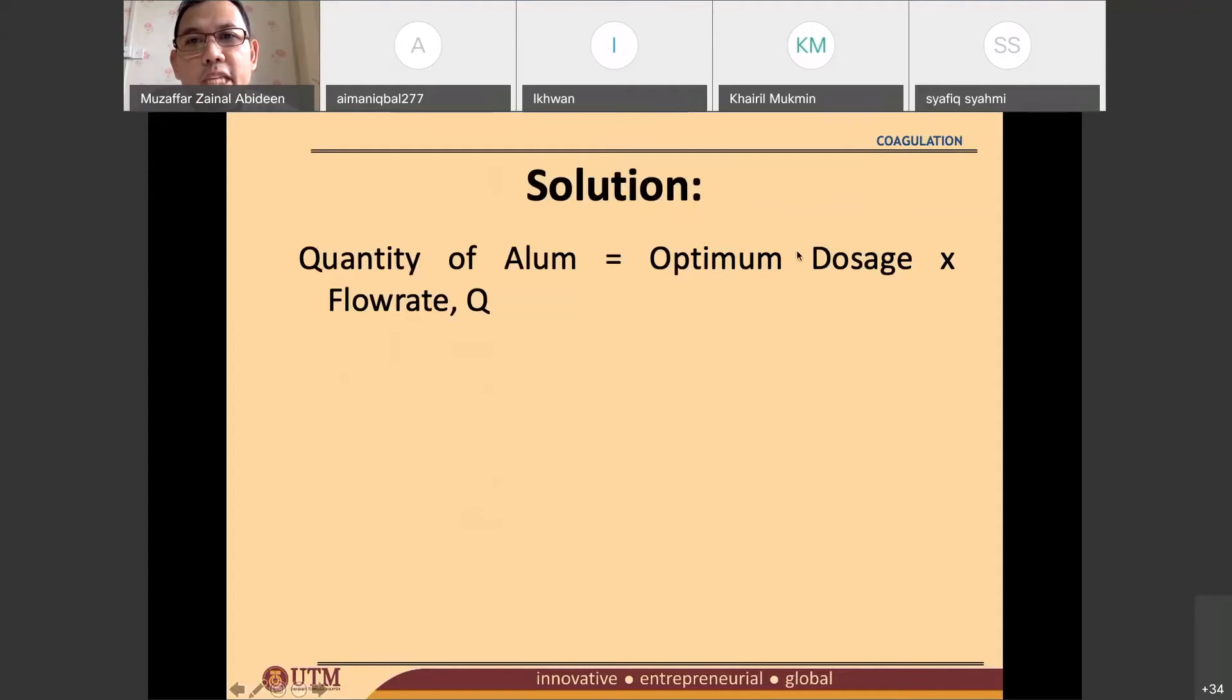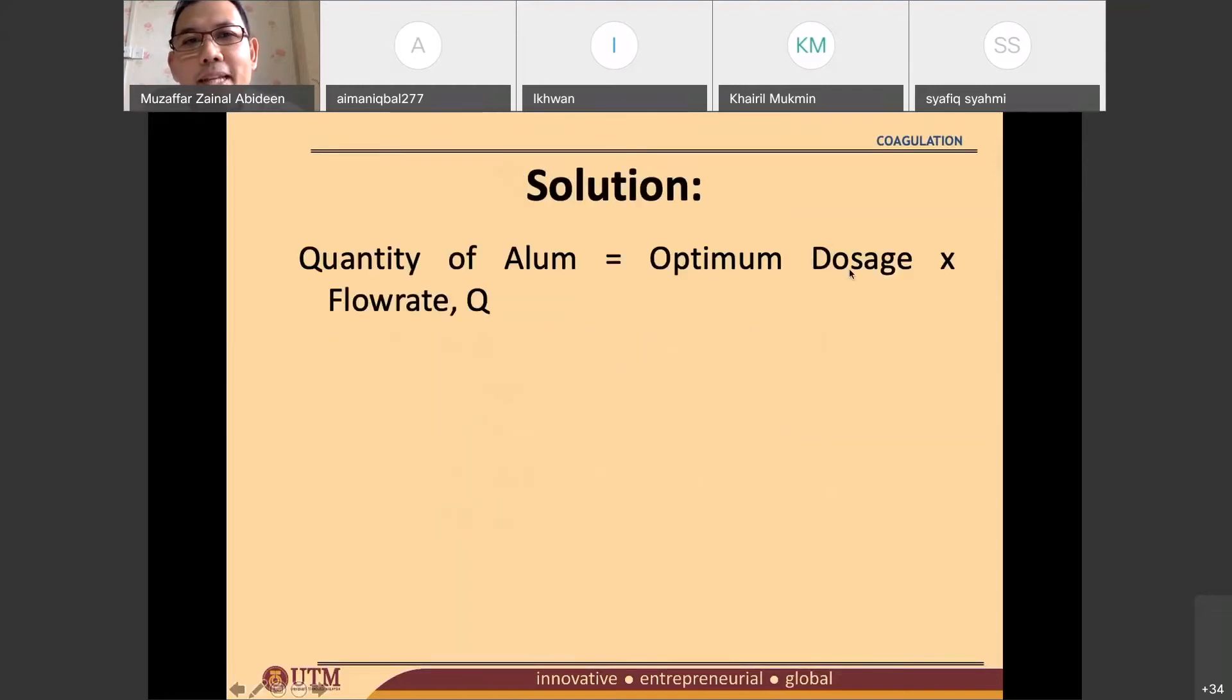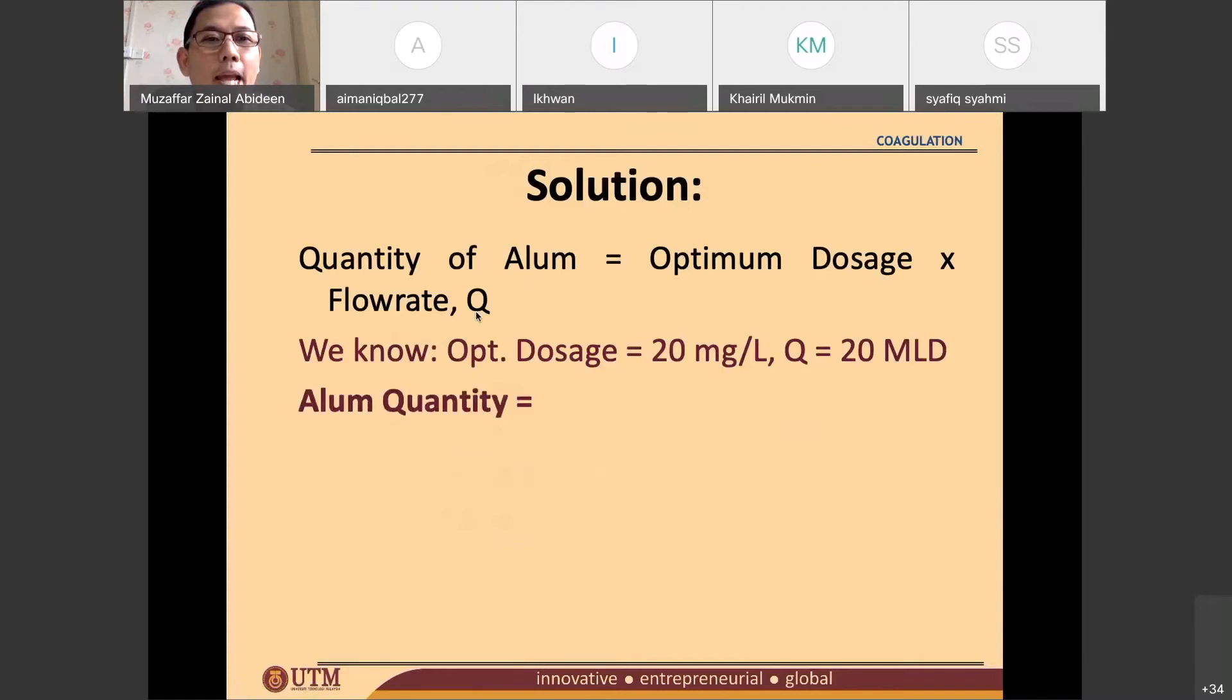So we look at the optimum dosage. It's being told already, right? So the optimum dosage was 20 mg per liter and the flowrate is 20 MLD. Therefore, we know that. And then the alum quantity is this value multiplied by that value. 20 mg per liter times with the flowrate, 20 MLD means 20 million liters per day.